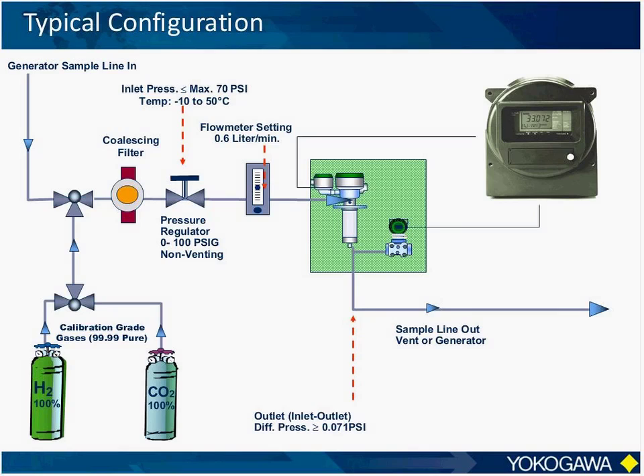And here's a typical installation or configuration for these applications. The sample from the generator is brought in through a system of valves, and they're configured to allow the selection of calibration gases. The sample is then passed through a coalescing filter to drop out moisture and a pressure regulator to knock the pressure to below 70 psi. A needle valve and a rotameter are used to control the flow of the gas between 0.1 and 1 liter per minute. From there, it flows through the detector, its pressure is measured, and then it can be exhausted to a vent line or back to the generator.